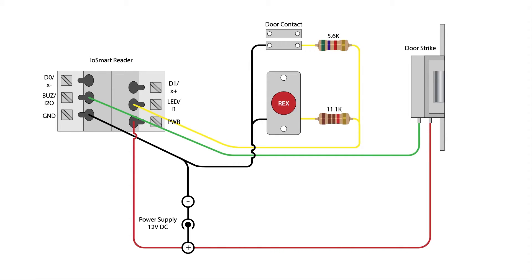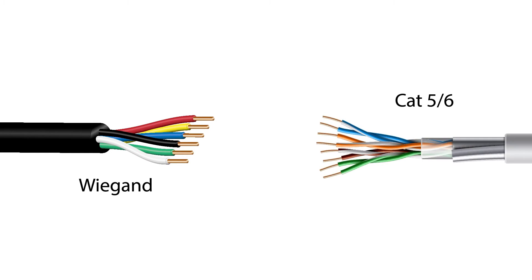This illustration depicts typical Wiegand wiring color schemes. If using Cat5 cabling instead, it is recommended to combine two conductors for each power terminal, such as orange and orange-white for positive DC voltage and brown-brown-white for negative.